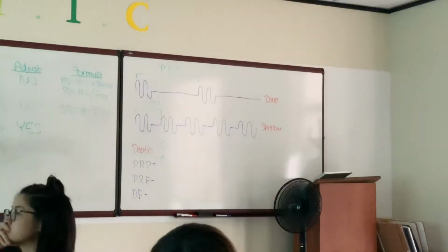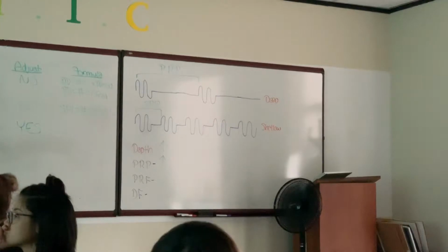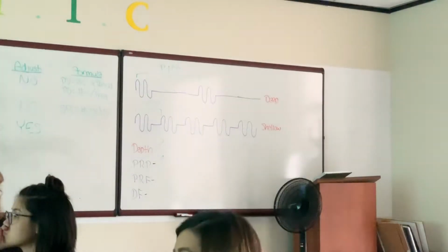When you are changing the PRP, are you also changing the frequency? Not the frequency of the transducer. We're changing the pulse repetition frequency, yes. But let me get there. That's the next thing. I want to make sure we're good on PRP first.